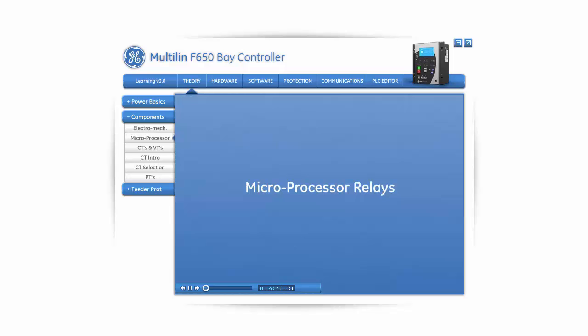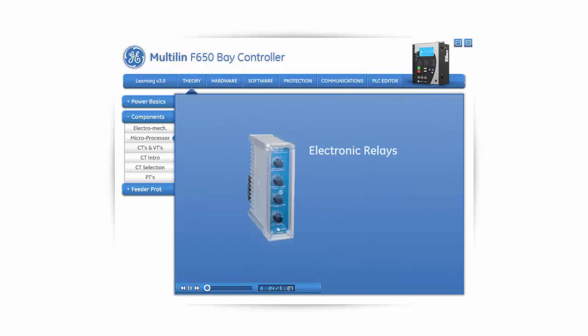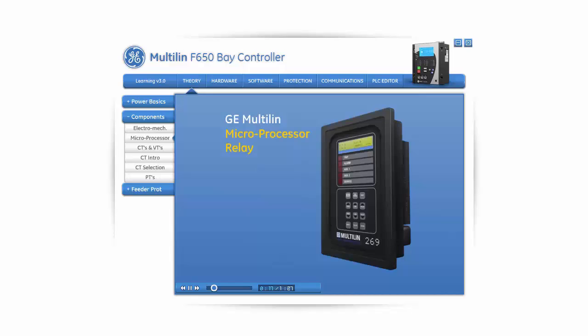In the 1970s, many relay manufacturers introduced electronic relays, which simply emulated their electromechanical predecessors, and in many cases, the design still required costly periodic calibration. In the early 80s, the microprocessor-based relay or digital relay was introduced. Standard features such as multiple element support, low maintenance, built-in high-speed communication, waveform, event log, improved element performance, and built-in programmable logic controller functionality have enabled the digital relay to revitalize the protection industry.